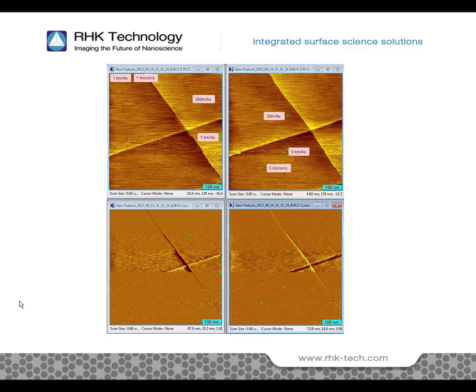This slide shows how parameter changes are displayed on the data. In this example, the Z feedback loop was decreased in steps and then returned in steps back to the original value. At each parameter change, a dot is displayed on the image showing exactly where that change was made. When you move the mouse over a dot, a box will pop up and show the changed parameter. Here you can clearly see when and where the feedback loop was changed and the effect it had on the image. Every other system requires the student to remember to write these changes down in their lab notebook. But even if they're diligent and follow their instructions to keep track of what they've done, they can never precisely show where on the image those changes took effect.